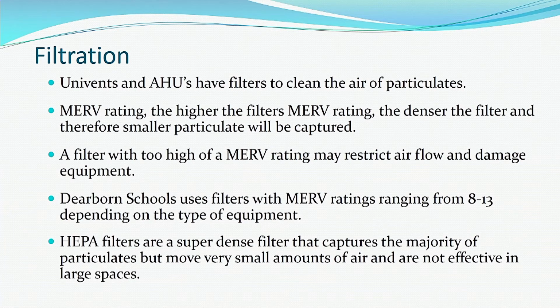Or, if the system's not designed for these higher levels, we can have bypass around the filters. So throughout the district, we've been evaluating filters, and filters are in the 8 to 13 MERV rating throughout the district, and we're continuing to work on that. HEPA filters are a super dense filter that captures a majority of particulates but moves very small amounts of air and are not effective in large spaces. Typically a HEPA filter is in a vacuum or a small countertop unit, and it's got a small fan. So it filters the air very well, but if it's only a small amount of air in the space, then the effectiveness is reduced with a small fan.